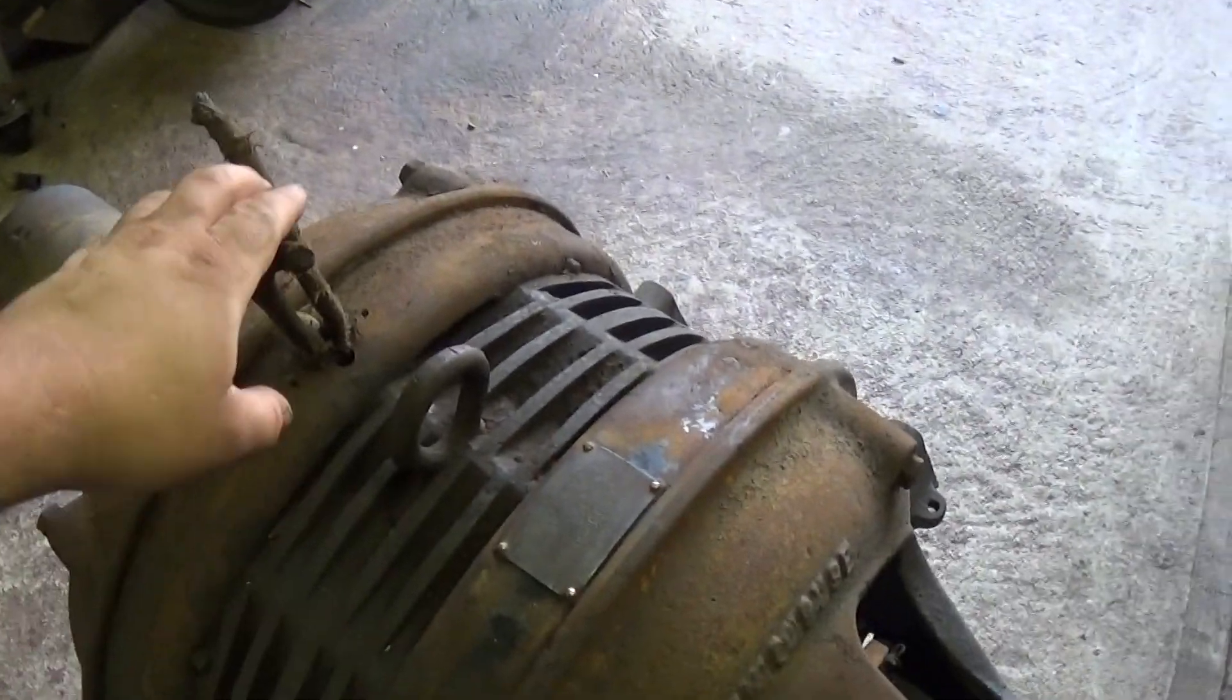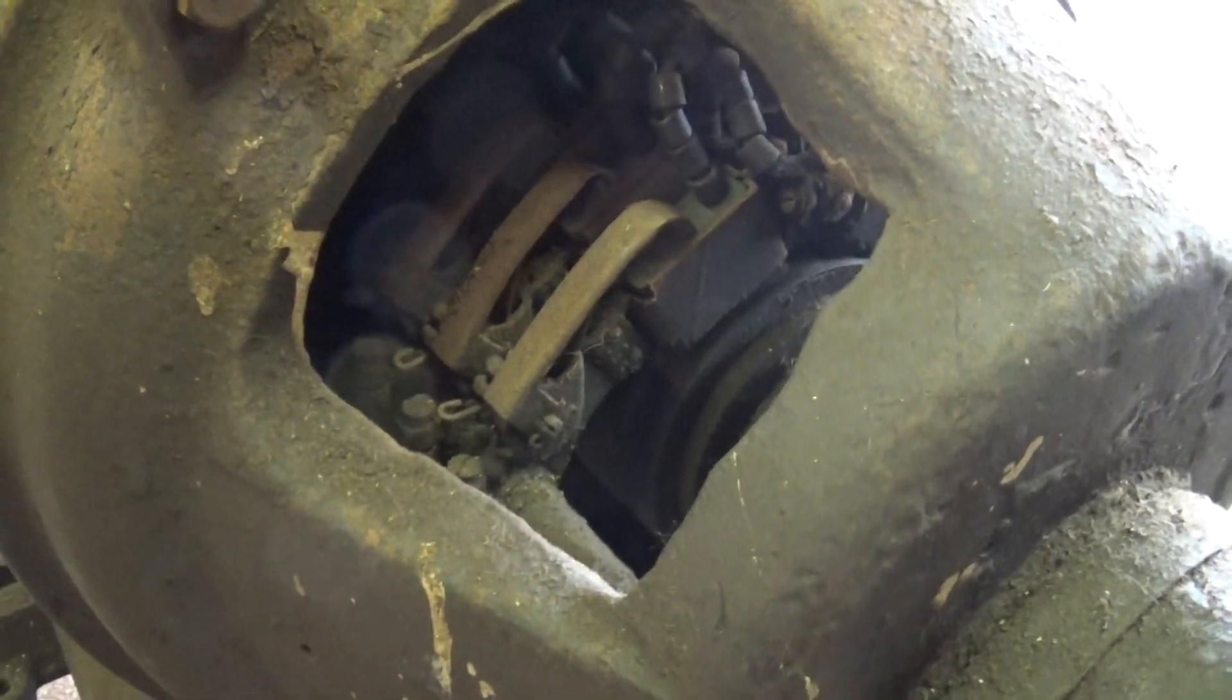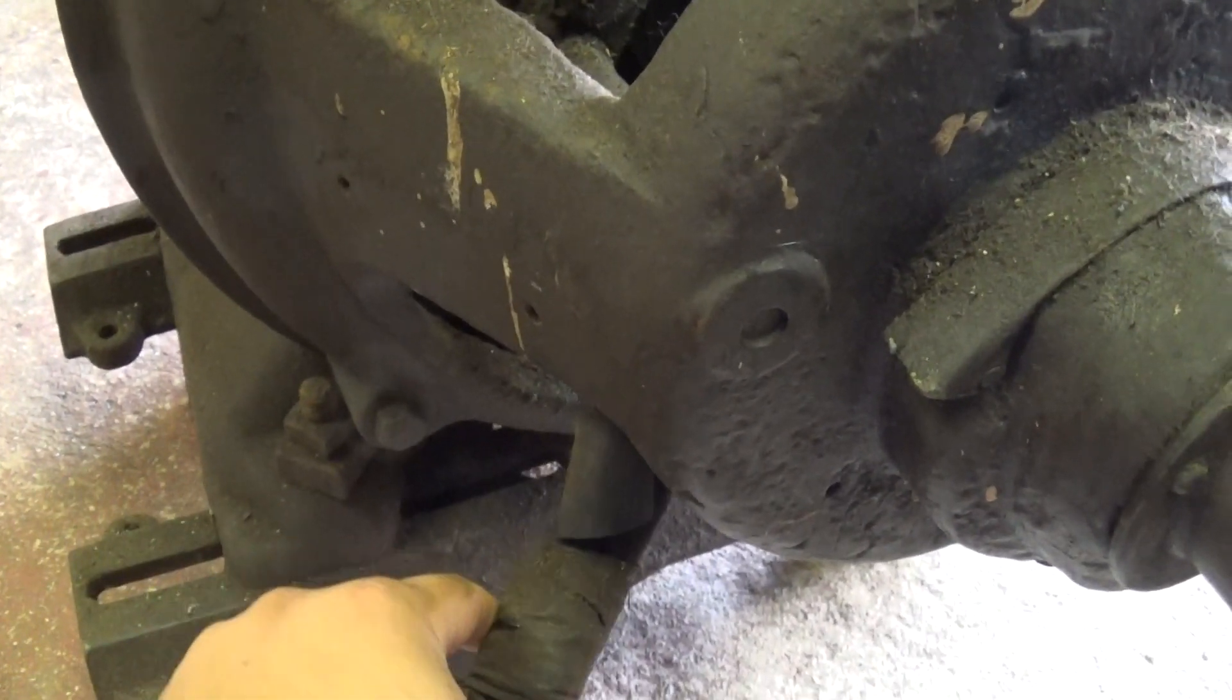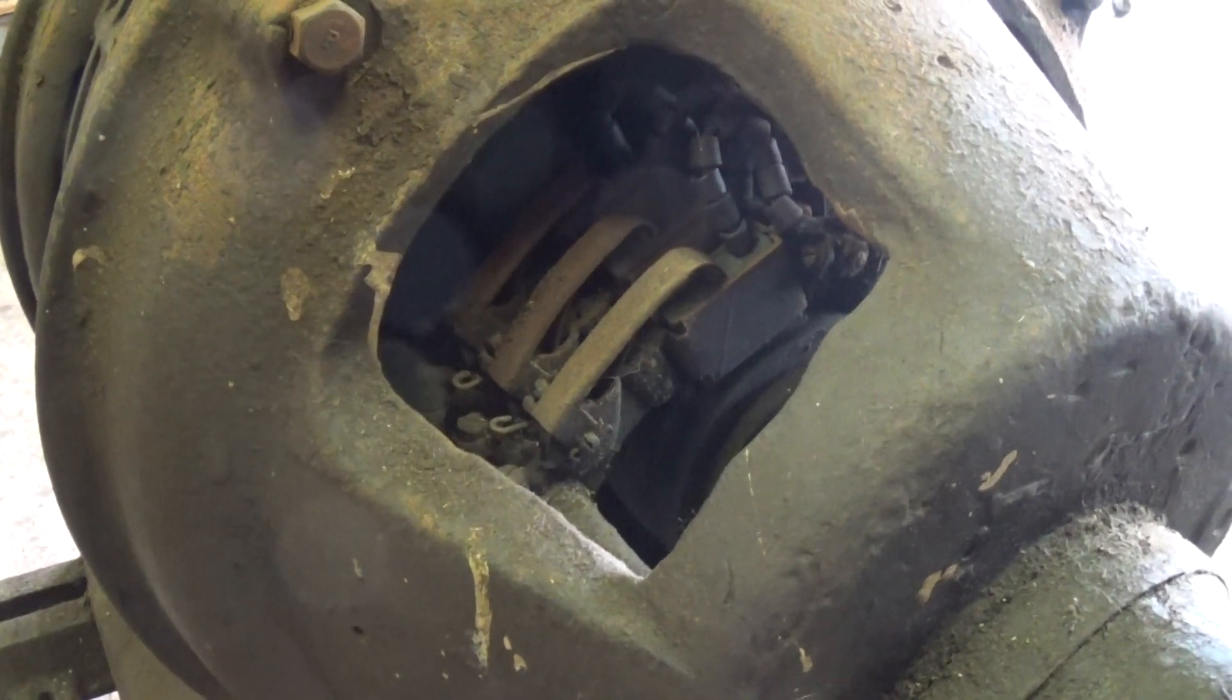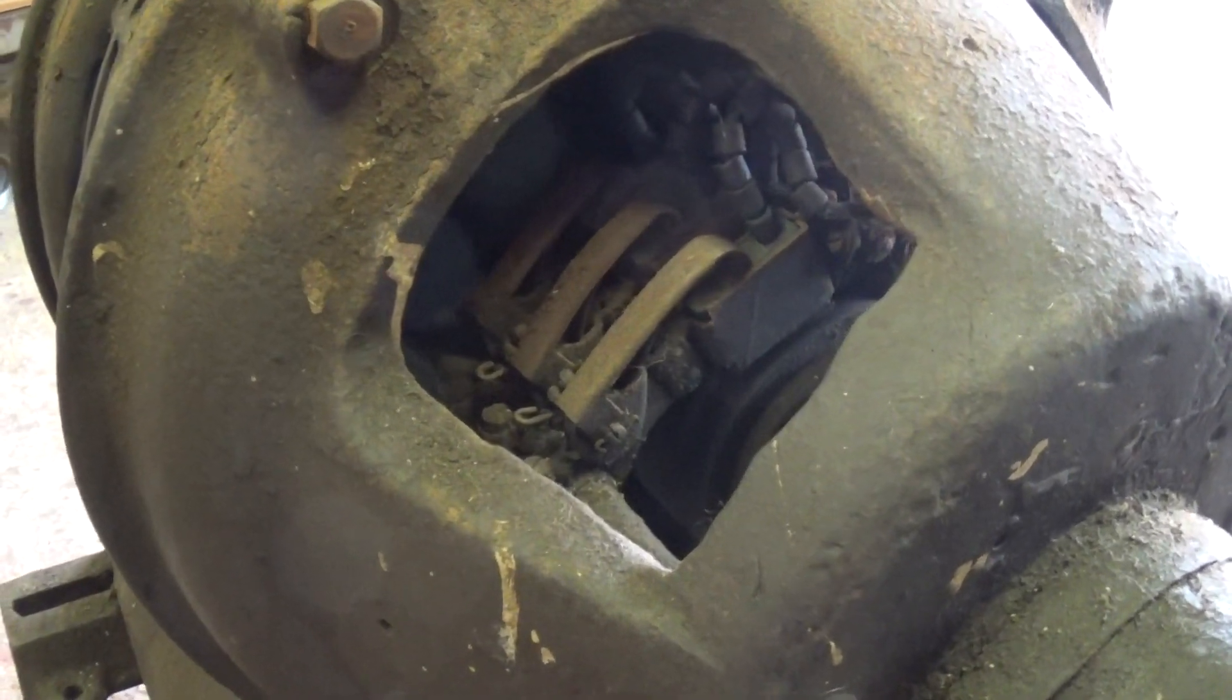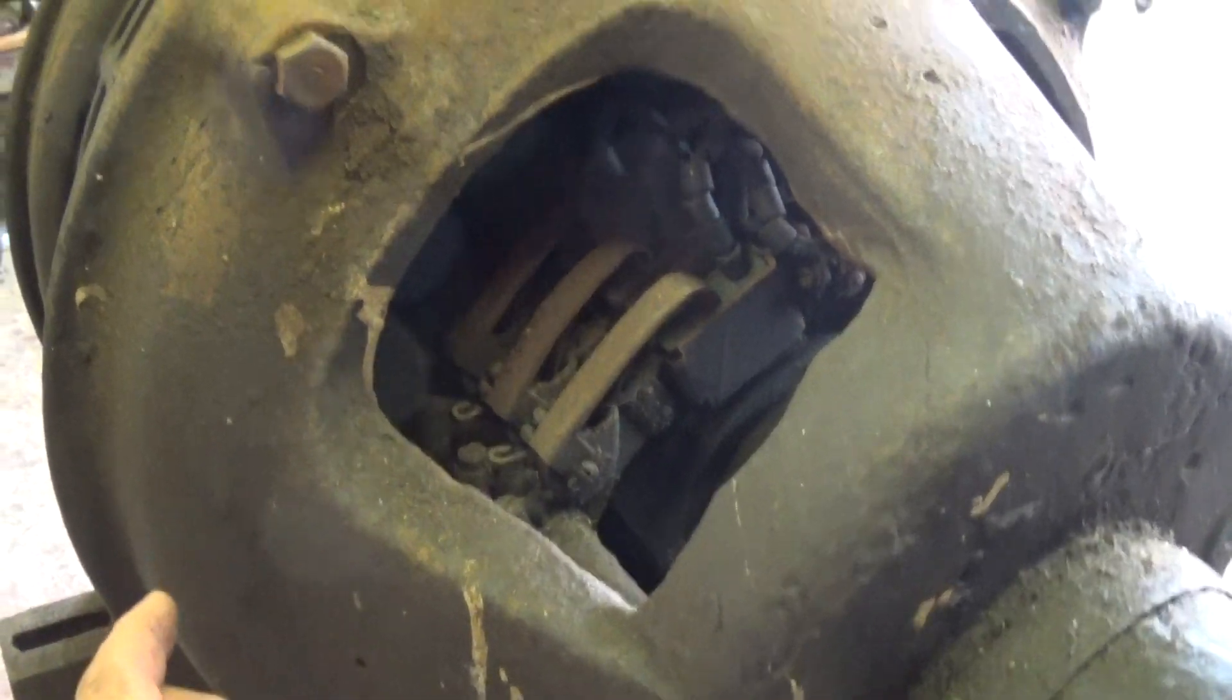So you've got three phase power coming in here to the stator. And then you've got three collector rings on the armature, or the rotor, and they're brought out here. And typically this would go to a triple ganged rheostat of some sort to vary the resistance in the armature windings. And varying that resistance would either increase or decrease the amount of slip the armature had with respect to the rotating field in the stator.